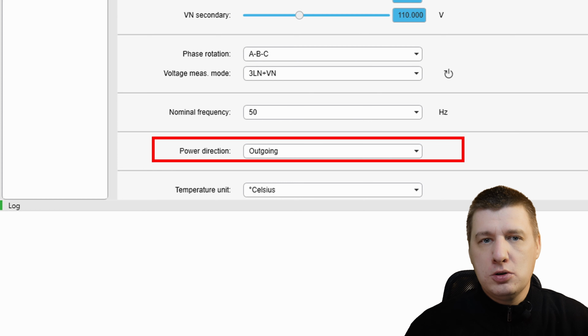Most circuits are outgoing feeders, according to standard practice. For outgoing circuits, power supplied by the busbar to the load is treated as positive. Conversely, any power flowing back into the busbar is treated as negative. This is the default setup for most distribution lines. Then we have incoming feeders like main transformers, incomers or generators. For those, the logic is flipped. Power supplied to the busbar is treated as positive. If the power flows away from the busbar to the source, the relay reads it as negative.